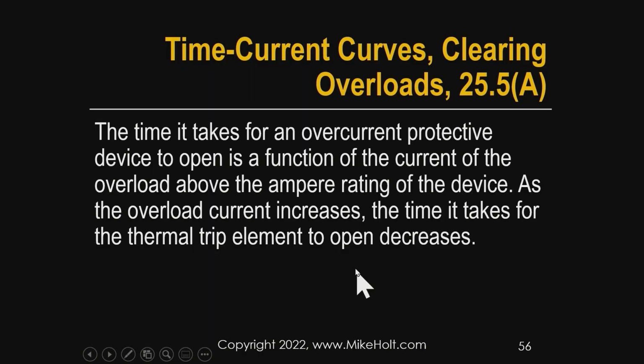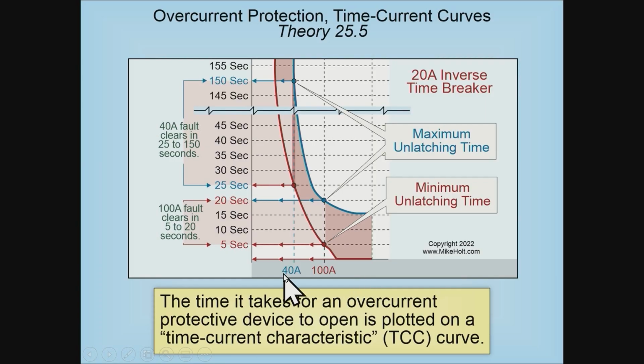The time it takes for an overcurrent protection device to open is a function of the current of the overload above the ampere rating of the device. As the overload increases, the time it takes for the thermal trip element to open decreases. I think we've established that, right? That was where we said, okay, at 40 amperes on a 20 amp breaker, 40 amperes is going to be between basically a half of a minute to 2.5 minutes.